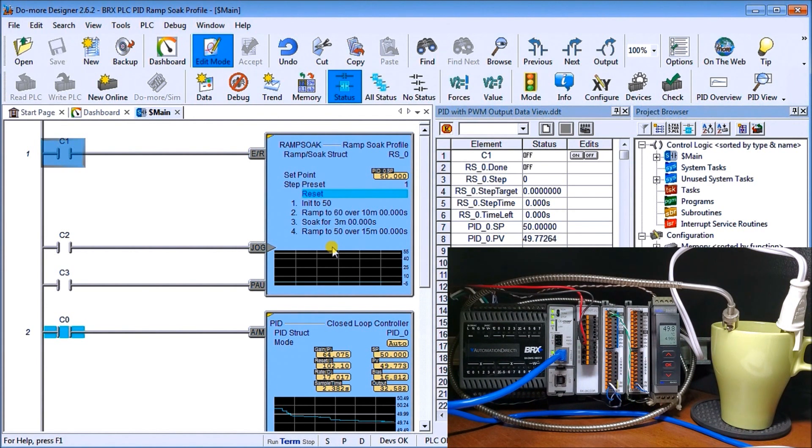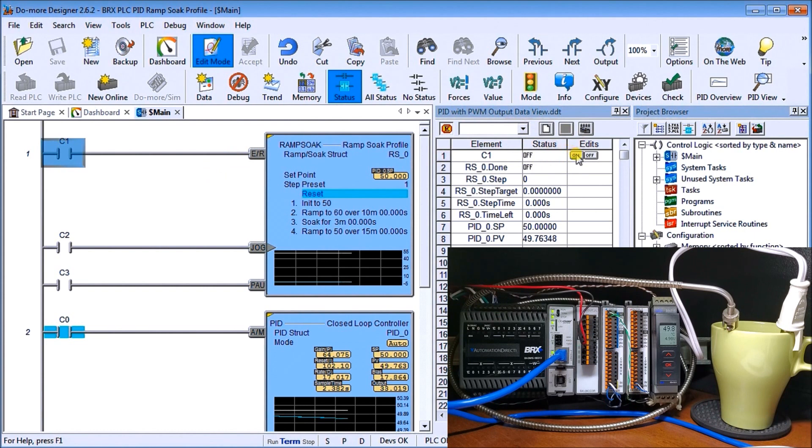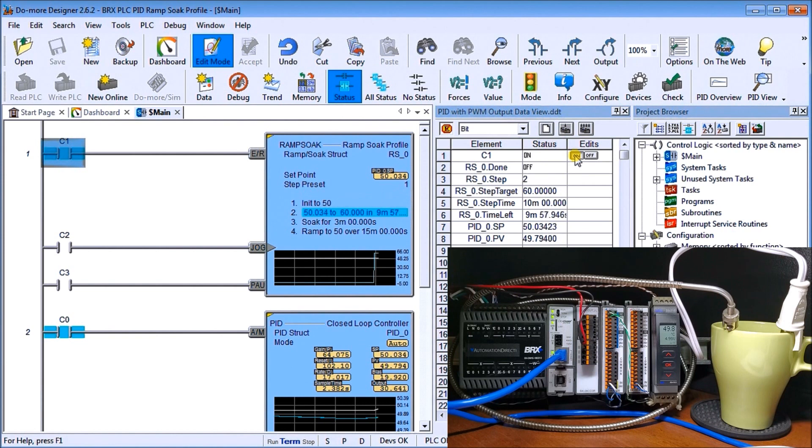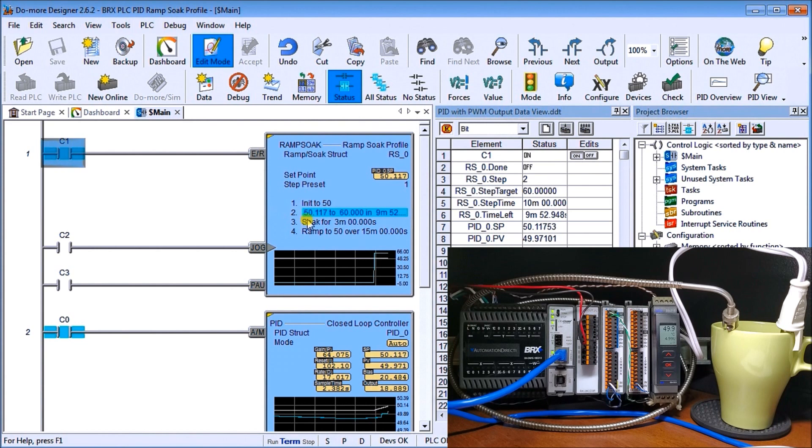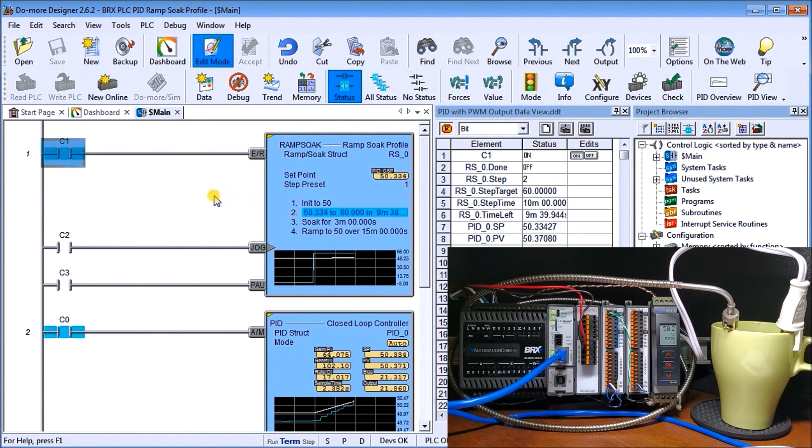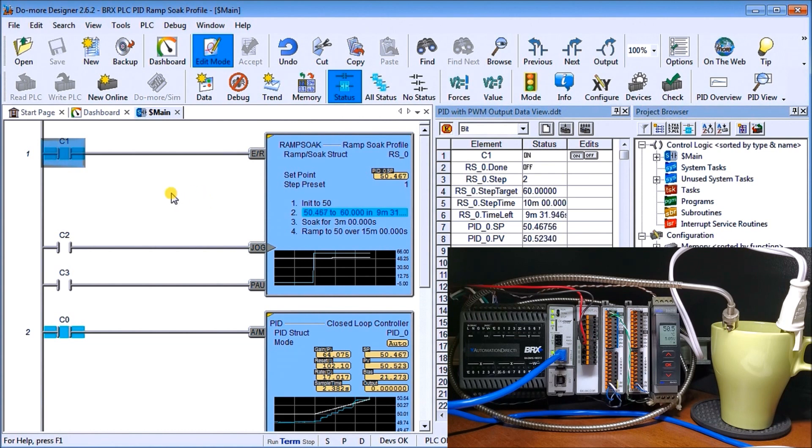So what we'll do now is we will start our, through our data monitoring here, we will actually turn on C1, which will then start our ramp soak. You'll see right now, we're currently a set point of 50. And when we turn this on, it'll start ramping up to 60 over the next 10 minutes. So we're starting to do that. And you can see as it's going along, we're actually ramping it up. And you'll see if my output's on right now, a hundred percent, so that it's slowly going on. So we're going to be ramping this up to that 60 degrees Celsius. Now, what we're going to do is speed up the video so that you don't have to wait this long for the ramp to actually happen.